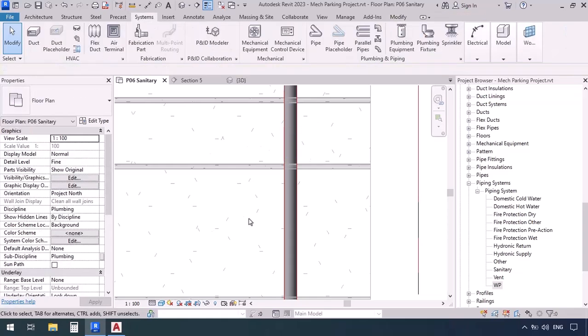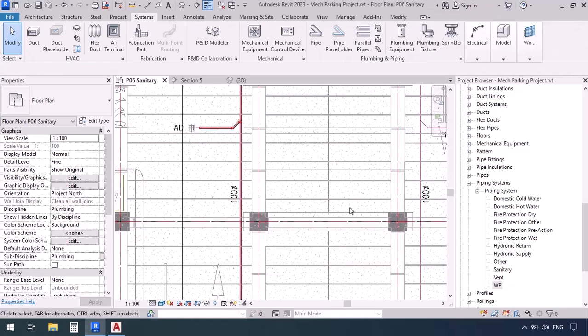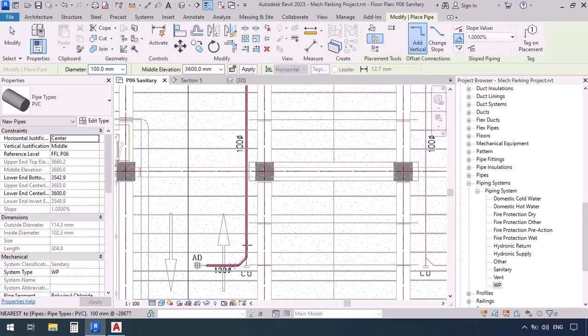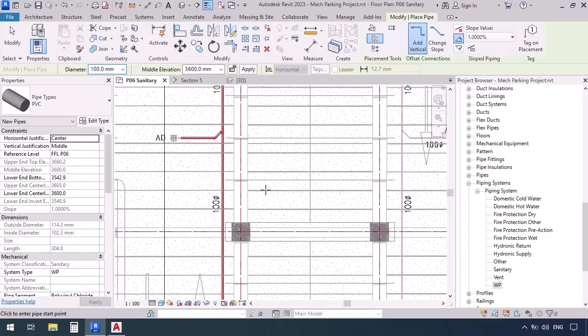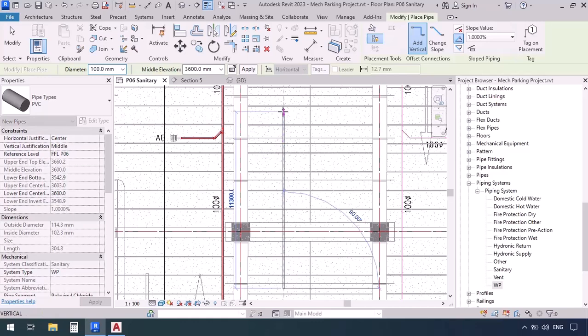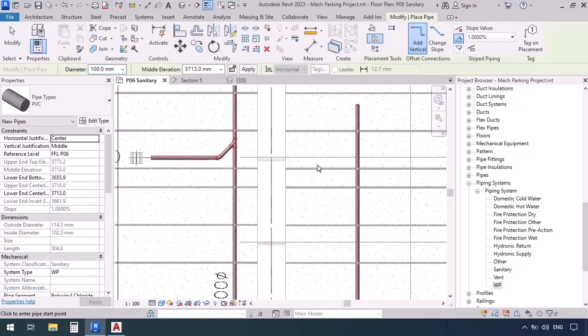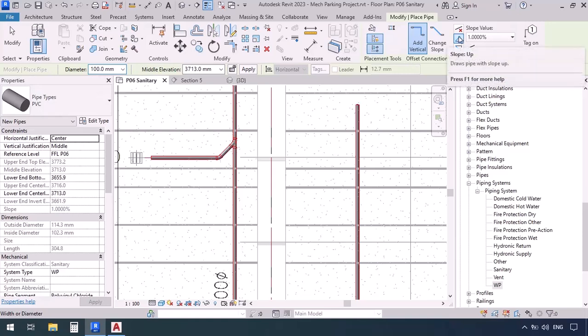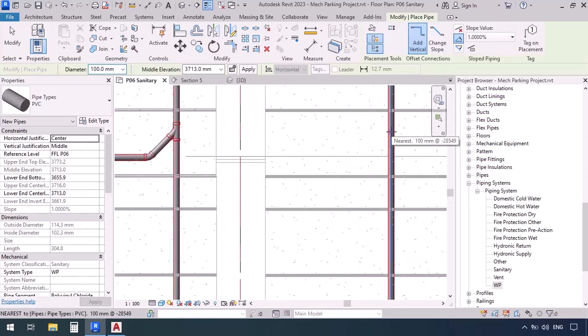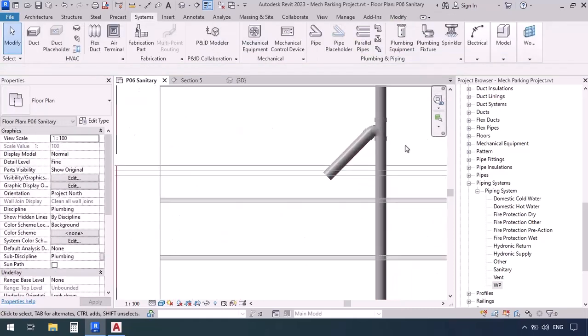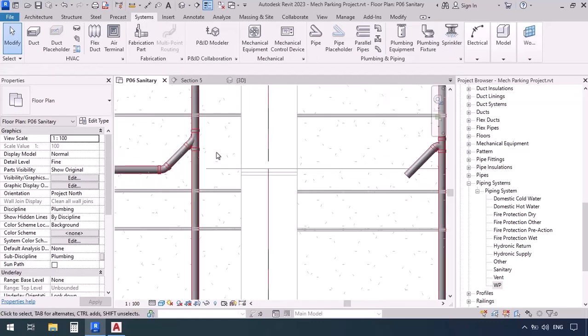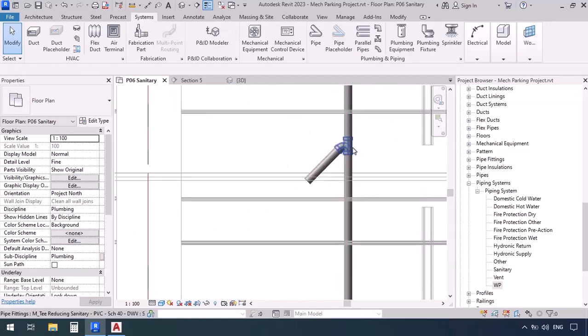Here's another thing. I'll get the pipe command PI. When we were trying to draw the pipe from the area drain to the riser, it was sloped down. Let's assume that we drew slope up by mistake. I just drew a slope-up pipe. Now here we want to draw a junction — PI. Remember the left-hand rule: fitting PVC, system type, adjust the sizes, use Inherit Elevation for elevation, and we're getting close to the drain so slope up. We'll think everything's okay and start to draw. Then we see that we got a strange shape — we don't have a proper T. In case you ever see a fitting that looks abnormal and unusual, you would know that the slope of your main pipe is wrong.